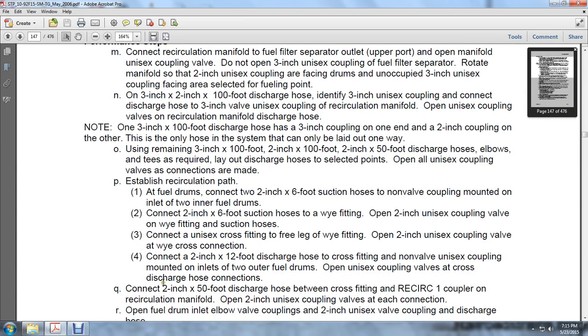Establish the recirculation path. At the fuel drums, connect two 2-inch by 6-foot suction hoses to the non-valve couplings mounted on the inlets of two fuel drums. Connect the 2-inch 6-foot suction hoses to a Y fitting. Open the 2-inch unisex coupling valves on the Y fitting suction hoses. Connect the unisex cross fitting to the free leg of the Y fitting. Open the 2-inch unisex coupling valve at the Y cross connection.